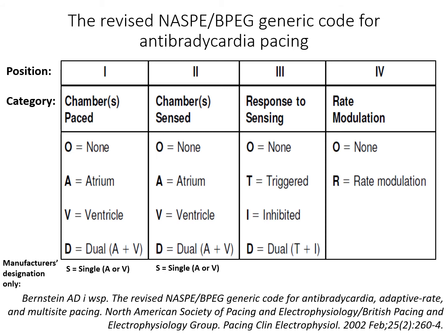For example, a conventional VVI cardiac pacemaker paces the right ventricle, senses the right ventricle, while in the case of sensed ventricular depolarization before a given lower rate of pacing, it inhibits pacing. However, if within a specified period of time resulting from the programmed lower rate, usually about 1 second, there is no depolarization in the ventricle, then it will deliver a pacing impulse.